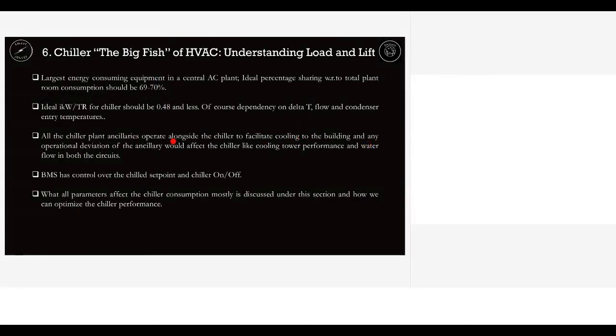The BMS, the IoT or Internet of Things based building management system, has control over the chiller set point and the chiller on-off. The chiller set point is the temperature of the cold water leaving the chiller to the building. So that's one point we control in the chiller, and the second part is the on-off control.